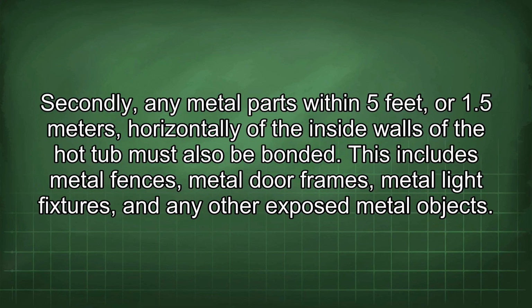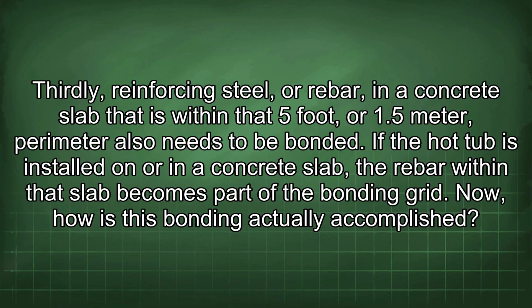Secondly, any metal parts within 5 feet, or 1.5 meters, horizontally of the inside walls of the hot tub must also be bonded. This includes metal fences, metal door frames, metal light fixtures, and any other exposed metal objects. Thirdly, reinforcing steel, or rebar, in a concrete slab that is within that 5 foot, or 1.5 meter, perimeter also needs to be bonded. If the hot tub is installed on or in a concrete slab, the rebar within that slab becomes part of the bonding grid.